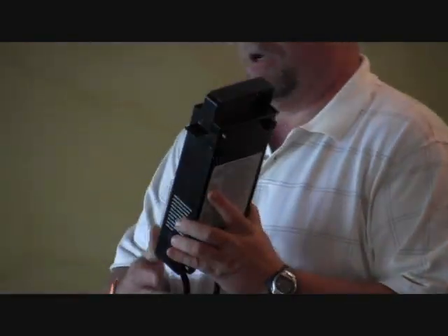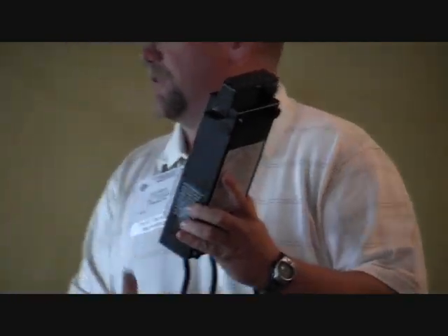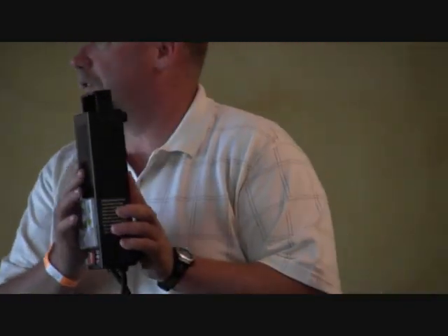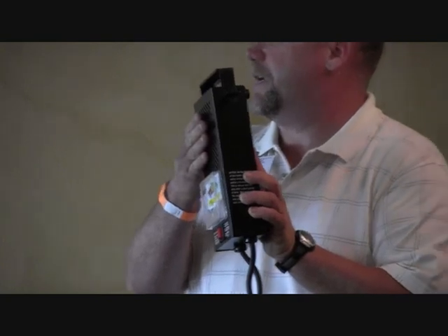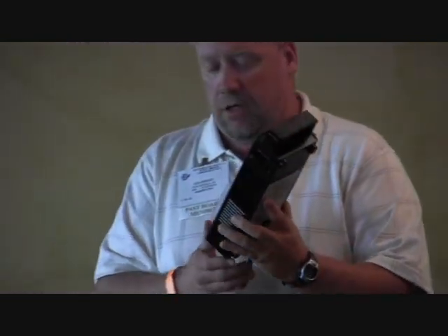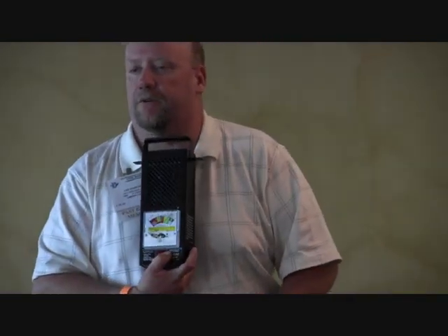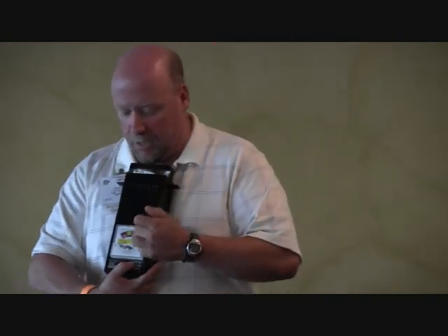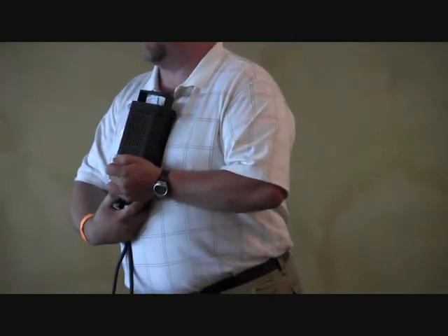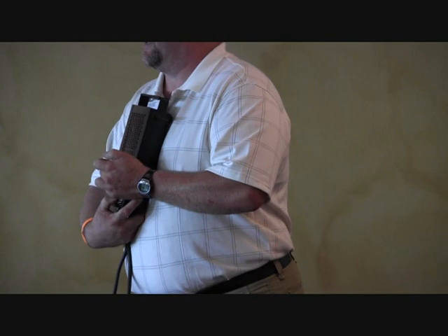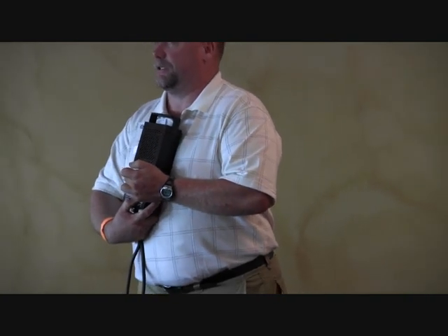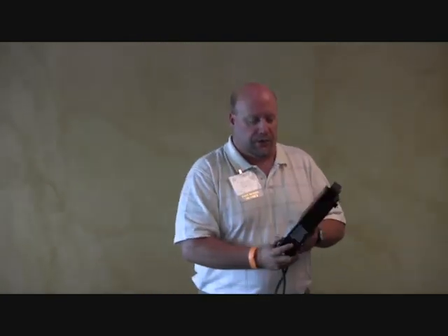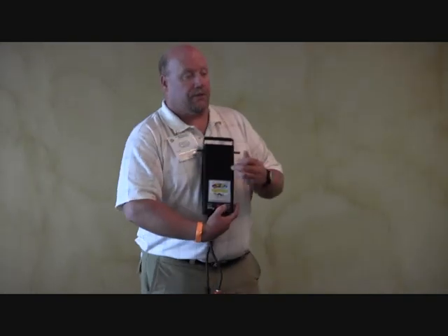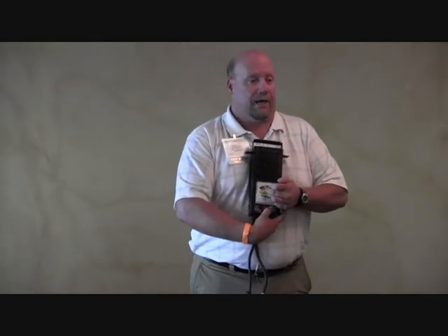You are literally jumping positive to negative through what they call a toaster. This thing will actually turn red and it'll smell. It gets hot. But you're loading the battery down for a specific period of time, and then based on the amp hours of your battery, you read the scale, and it tells you the battery's condition. You're looking for a percentage, but it's pretty self-explanatory - good, weak, bad.